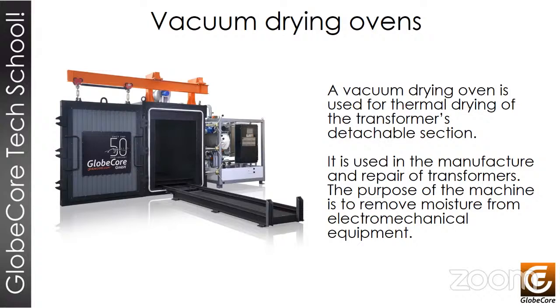The efficiency of processing the transformer's active section should be evaluated not only in terms of attaining a sufficient dielectric strength during tests, but also in terms of extending the service life and enhancing the operational reliability. The cost of processing is determined by its duration and quality, as well as by the installation characteristics to be attained. The ovens are used in manufacture and repair of transformers.